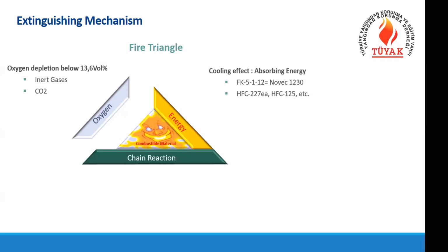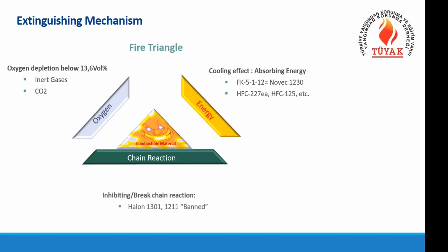By using inert gases and CO2. And we have the other gases like FK-5-1-12, which is NOVEC 1230, and HFC-227ea, like FM200. So these are also chemical gases, which are not inert gases. So here we are absorbing a lot of energy from the room, like refrigerating, cooling gases. So we are discharging these gases inside the room, and we are removing a lot of energy from the room. So the fire stops.